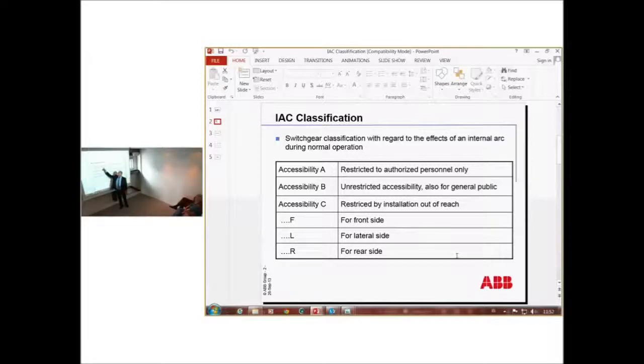But for a standard switchgear, in our case, it will be IAC, AFL, followed by the number 16 kiloamp, 1 sec. So then you are protected as an operator. If you are the operator standing here, operating the switchgear, you are protected in the front and to both sides.